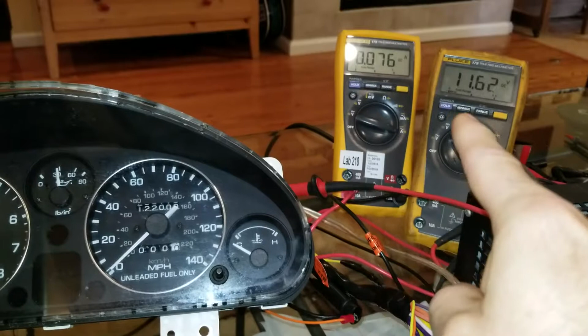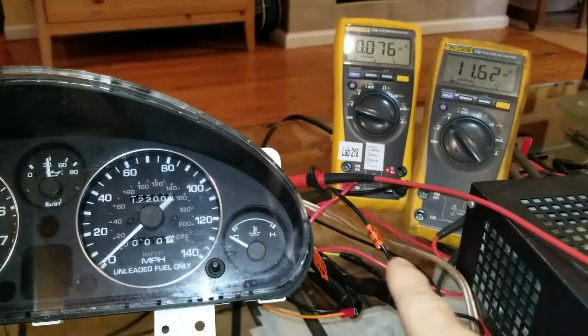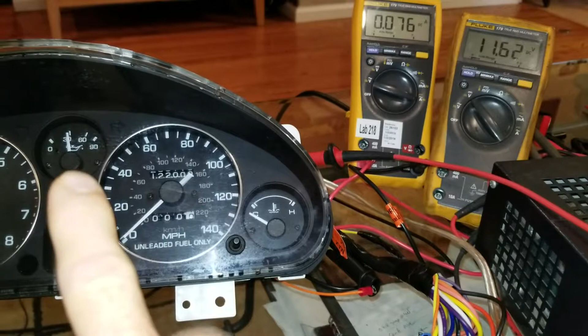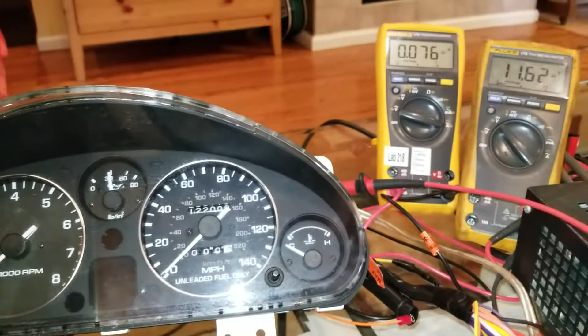What I'm going to show here is the current we're drawing from the oil pressure sensor pin on the gauge assembly, along with a simulated battery voltage. I can run this through various test modes, setting it to 30, 45, 60, or 15 psi. Right now it's set at 30 psi.